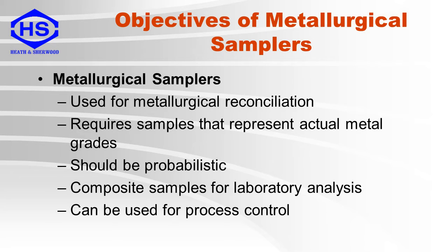Metallurgical samplers are used for metallurgical reconciliation. They require samples that represent actual metal grades. They should be probabilistic, meaning that every particle from the sample lot should have an equal probability of becoming part of the sample. These samplers produce composite samples for laboratory analysis, and they can also be used for process control.